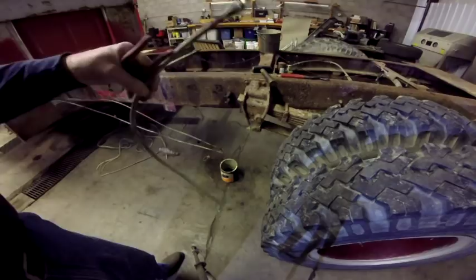Let me bring you back. I've got to get something to hold that copper line so it stops turning with the flare nut. Here's one of the pieces of copper that went from these fittings over to the pump. Piece number two. Okay, here we are disconnecting the line from that exchanger.